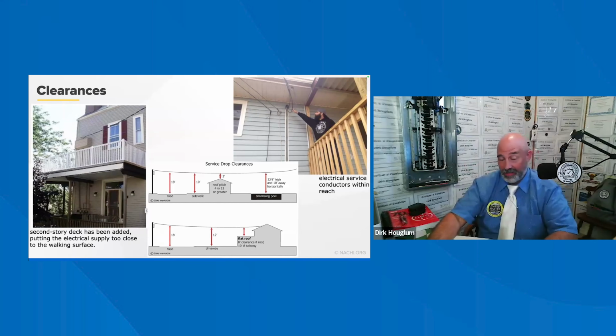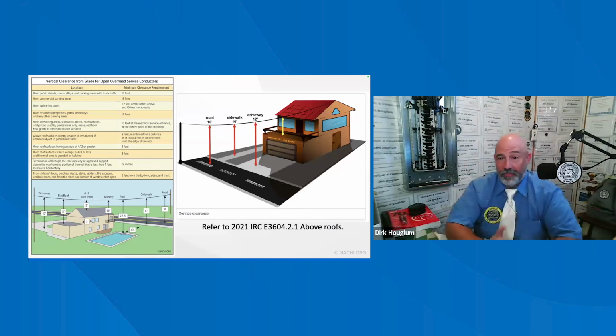True story. Scary. Conductors must have a vertical clearance of at least 8 feet above the roof surface with a distance of at least 3 feet in all directions from the roof edge. The NEC 230.24 if you want to check on that, okay?